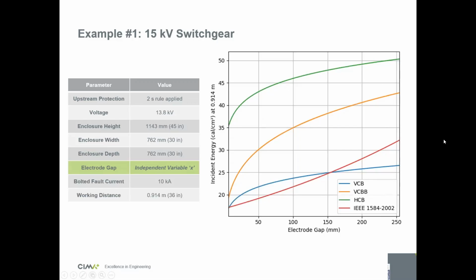What about the gap? Well, the gap has a big impact. When your gap is lower, your energy is lower, and if your gap goes up, your energy goes up. You can see here HCB is still the worst, then VCBB, and then the old IEEE version and the VCB have a somewhat similar curve shape.